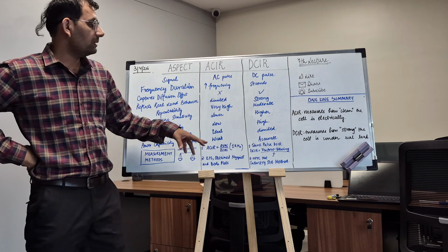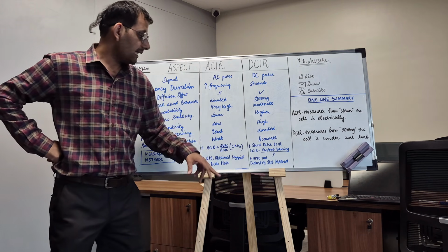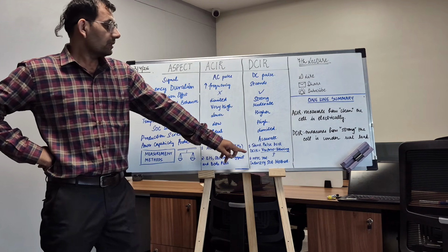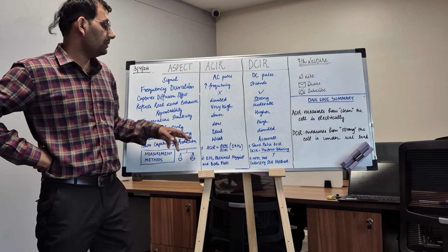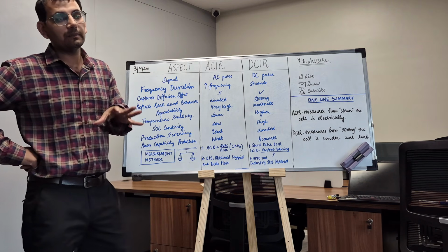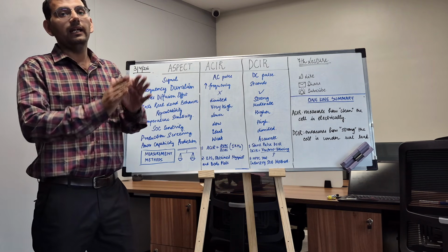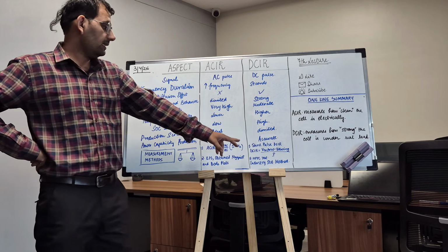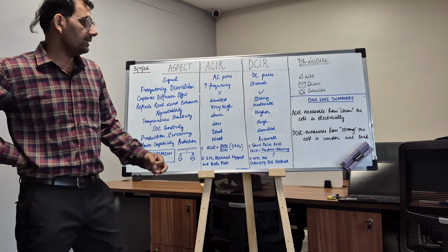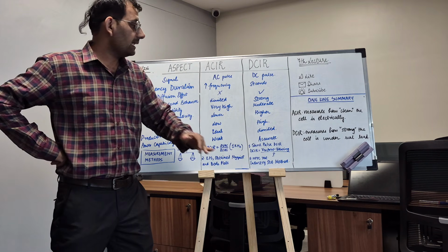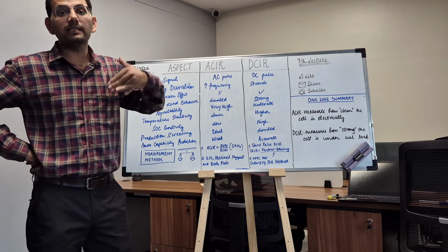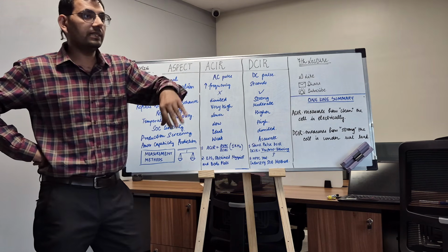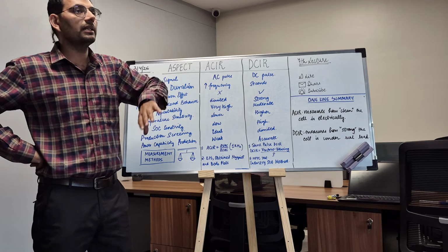DCIR also has two common measurement methods. One is short pulse DCIR, one is the HPPC test, an industry standard method. In the HPPC test we are finding the power capability prediction, how the cell's power capability is with respect to cell SOC and with respect to cell SOH, state of health. इसमें एजिंग का फैक्टर आता है, आपने कितनी साइक्लिंग एजिंग और कैलेंडरिंग एजिंग की है, कि कहीं ना कहीं अगर एजिंग होती है तो आपका IR, इंटरनल रेजिस्टेंस बढ़ जाता है. There is an increase in internal resistance if we are continuously using the cell cycling or doing some calendar aging.